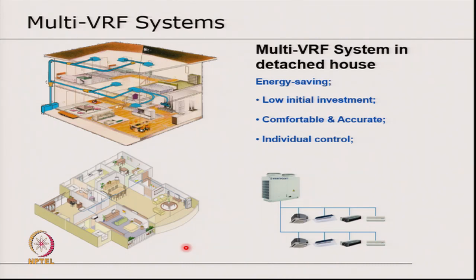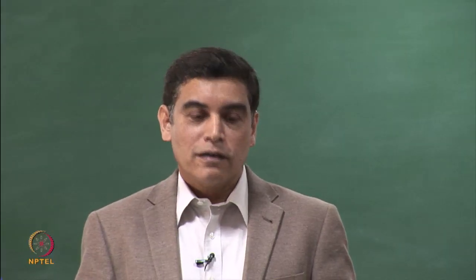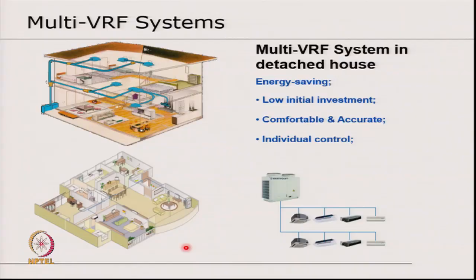Then we look at multiple VRF systems, and the whole value proposition for a VRF system is the ability to get annual energy savings. So in this figure we can see multiple indoor units. We have several of these terminal units all connected through a common piping and distribution of refrigerant.